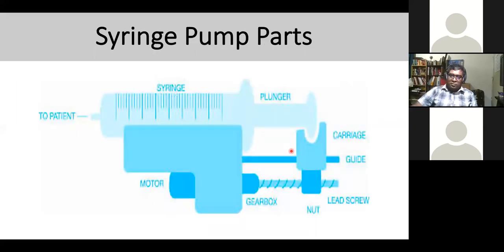So here are other photos of syringe pump parts. You can see the gearbox. The motor is normally a stepper motor. And you can see the lead screw and the nut and the guide line and carriage and the plunger and syringe to the patient. So what happens is this screw, when the motor moves, is going to move the carriage and the guide is going to support the carriage to move in a straight line in the proper way. It then moves the plunger, and the syringe will, when the plunger starts to move, you're going to get some output of fluid going to the patient with certain pressure and flow. That's how it works.